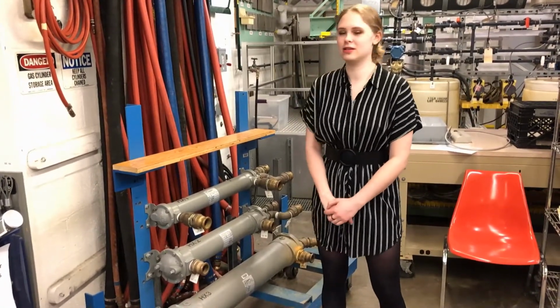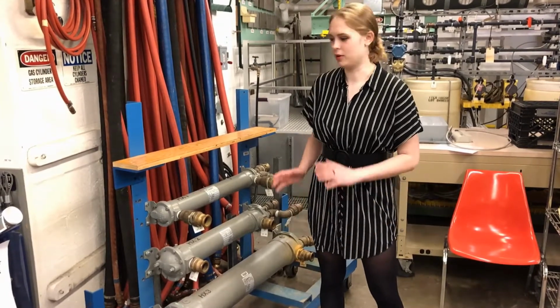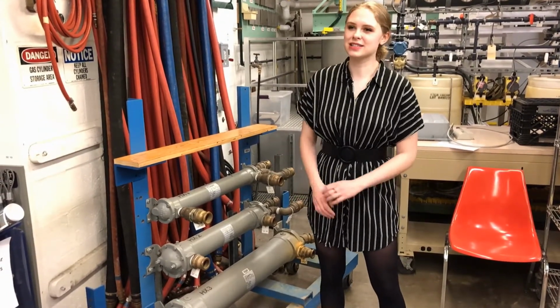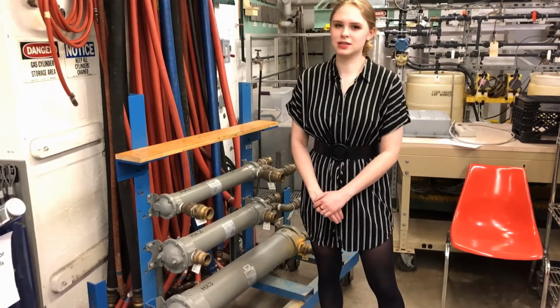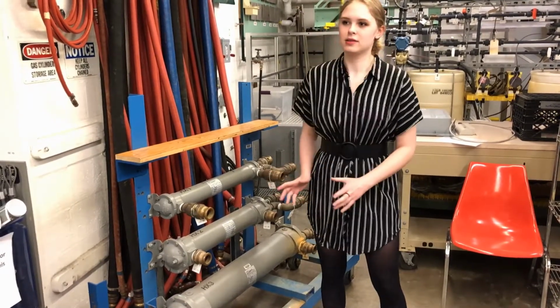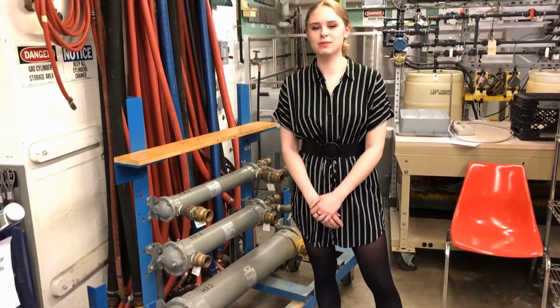Another type of heat exchanger is the shell and tube heat exchanger. In these heat exchangers, there are a lot of small tubes that are inside one large shell. Fluid passes through the smaller tubes in one direction and the large shell in another. But to prevent regions of stagnant fluid inside the shell, there are blocks called baffles that force the fluid to move in a pattern.